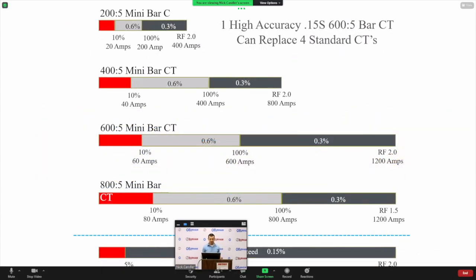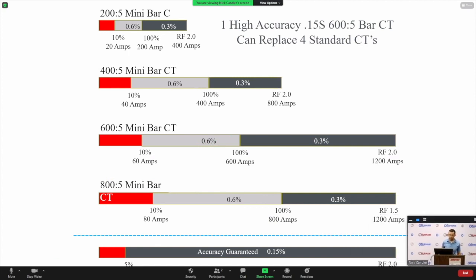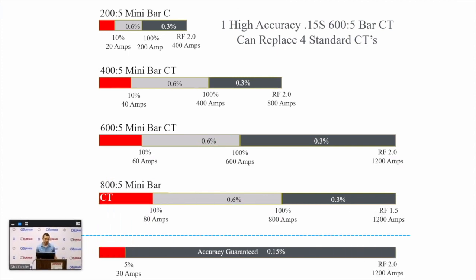was tested this morning. So here's an example of a high accuracy transformer and how it might replace a number of other transformers. There is a large value associated with this because you can stock one low voltage transformer and cover quite a few or most of your transformers that you're going to use.